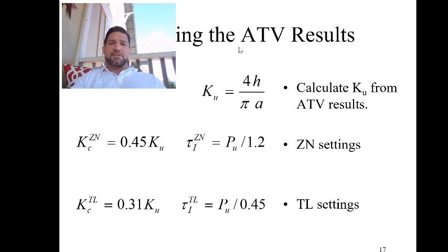So the way that we use the ATV results is first we calculate the ultimate gain. So KU is going to equal 4H, which is the change in the controller, divided by π A. A was the amplitude of the oscillations. And then based on this we can calculate the value of the gain and the τI using these terms. The period of oscillation which is shown on the previous slide and KU which is calculated here.